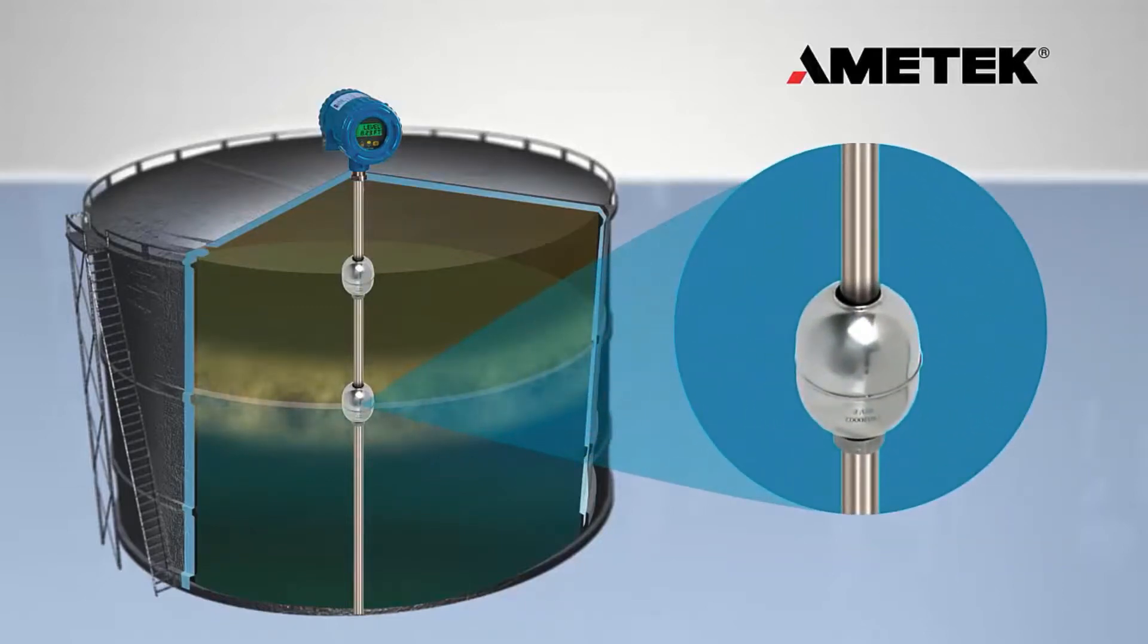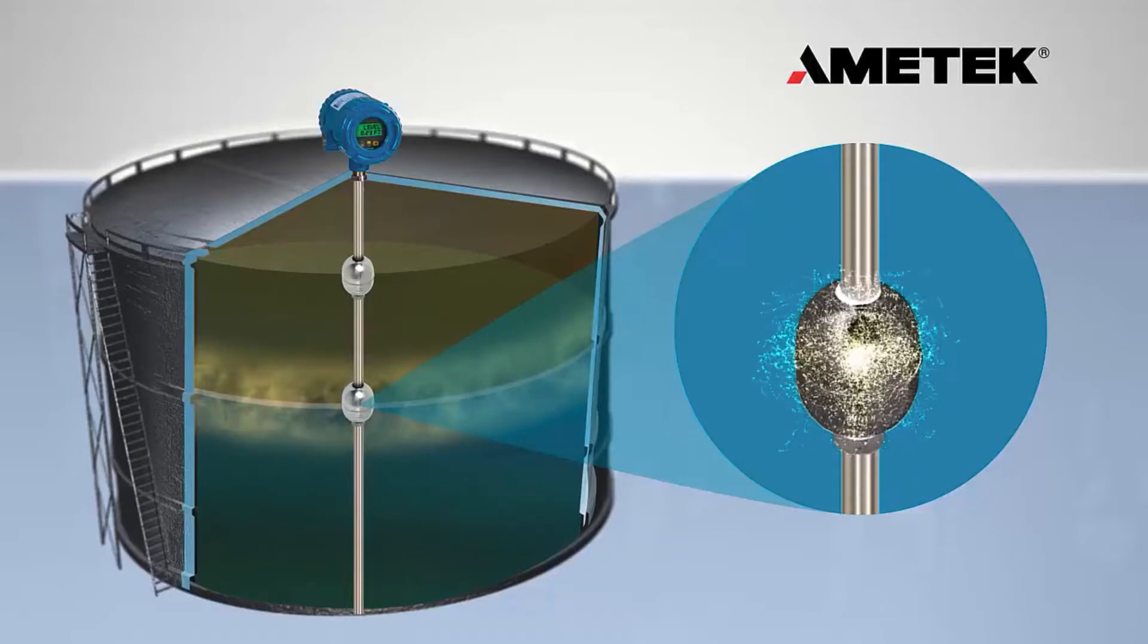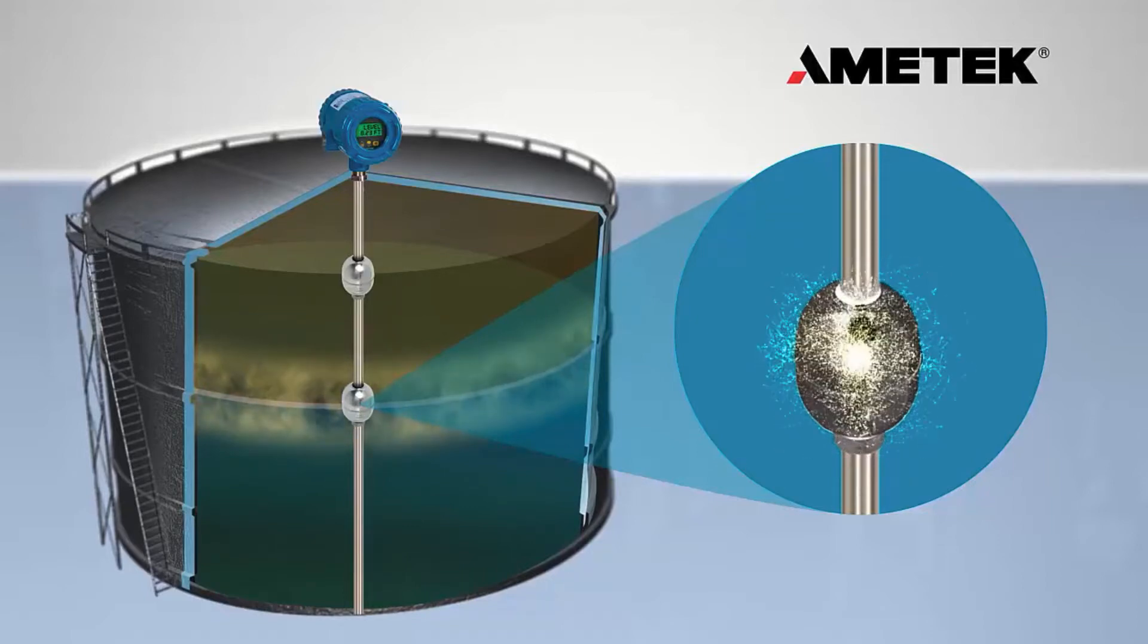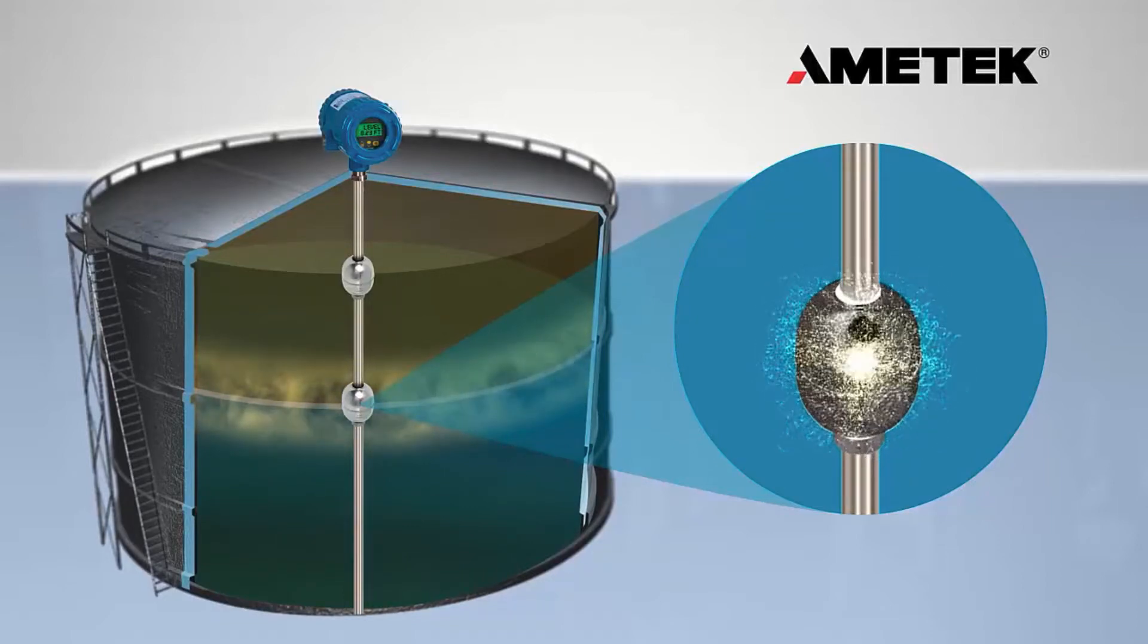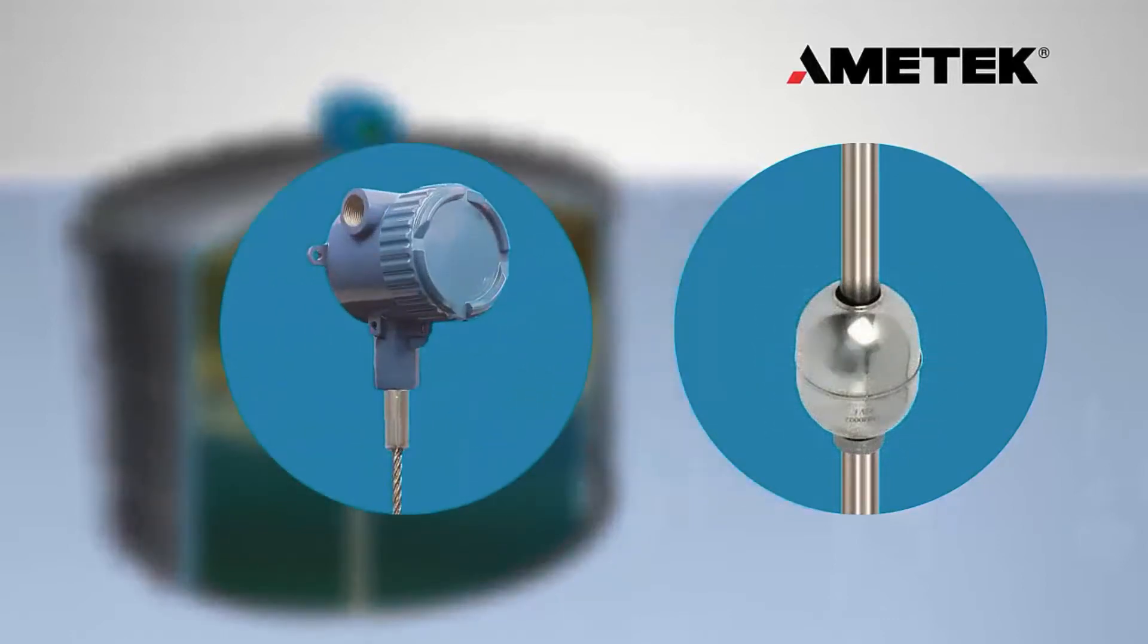Floats are positioned on the probe based on their specific gravity match to the liquids being measured. This ensures that the float will always maintain its position, both on the top liquid level and at the interface position. The lower measurement signal remains unaffected by the formation of an emulsion.